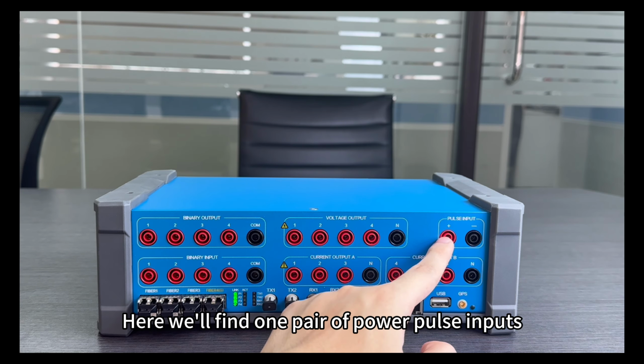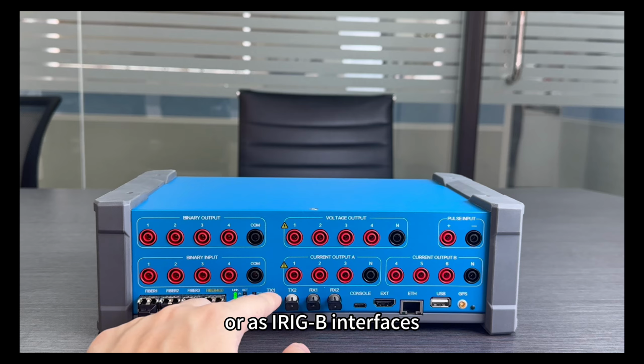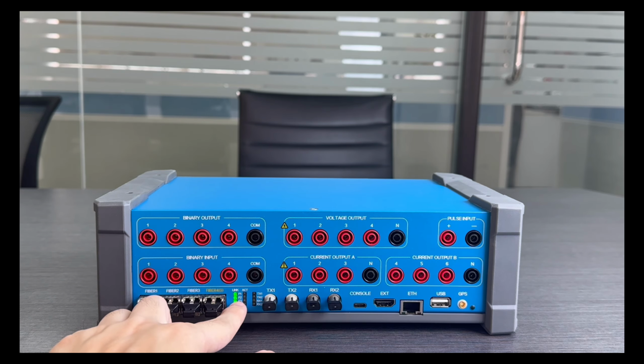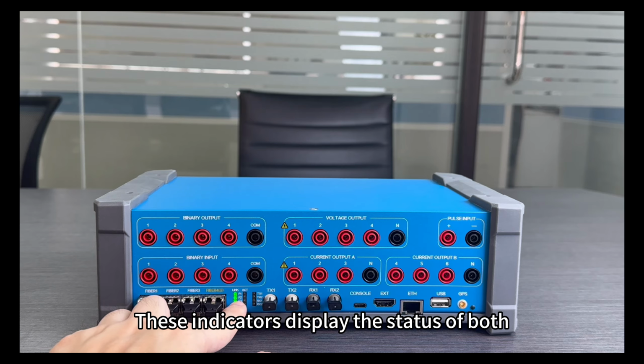Here we have 4 FT3 interfaces, with 2 dedicated for transmission and 2 for reception. These flexible ports can be configured to operate either as FT3 message transceivers or as IRIG-B interfaces. These indicators display the status of both fiber ports and FT3 interface. The console port is reserved for debugging and troubleshooting only. Next to it is an HDMI expansion port, designed for future upgrades and additional functionality.